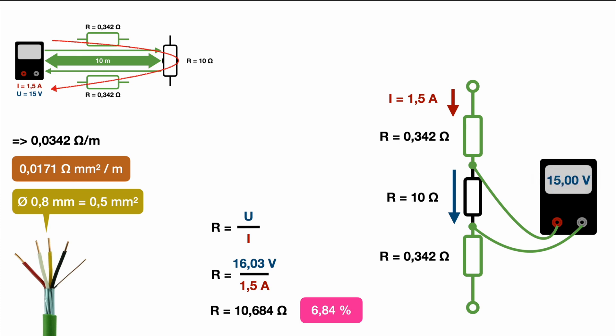And this measurement would be exactly 15 volts in theory so we would end up with those 10 ohm as soon as we divide it by 1.5 amps. So that's basically the difference between the two and the four wire technique. But I think there's a very important point a lot of people skip through once they're explaining the difference between the two and four wire technique.